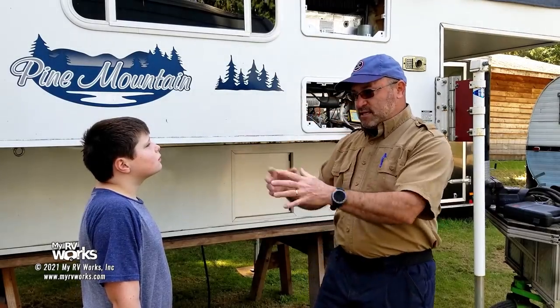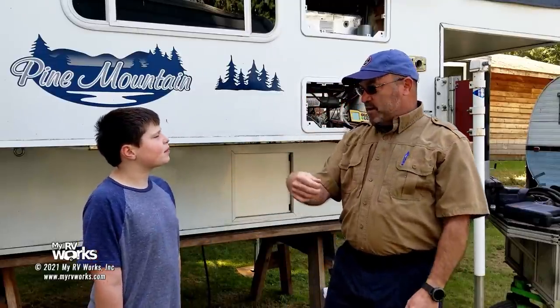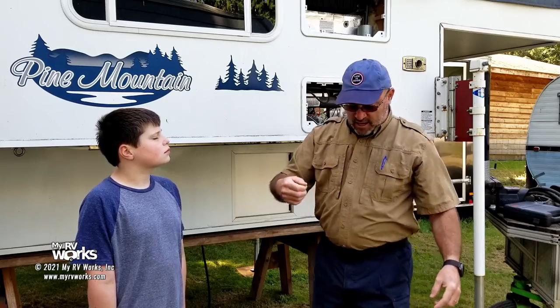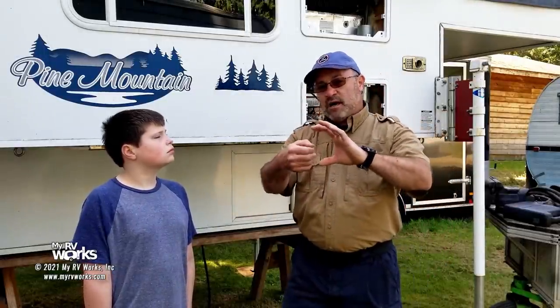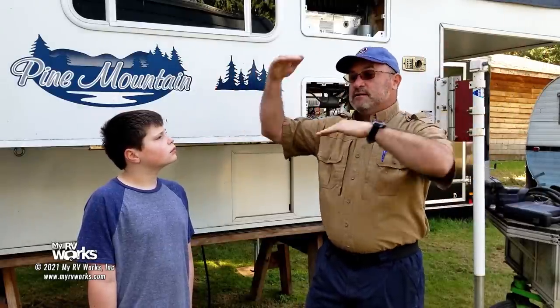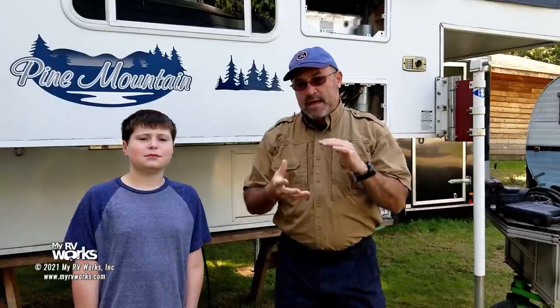So let me put this in an analogy. Let's say it's minus 44 out here, wearing our short sleeves, and I'm walking around with a cup of liquid propane. It's minus 44 degrees, and it's liquid propane right now. I go into the next room, and it's warmer than minus 44. It's minus 43 or minus 42. That one cup of liquid propane will vaporize to 270 cups of vapor. Okay, so as a compact energy source, you begin to see how tremendously compact it is.